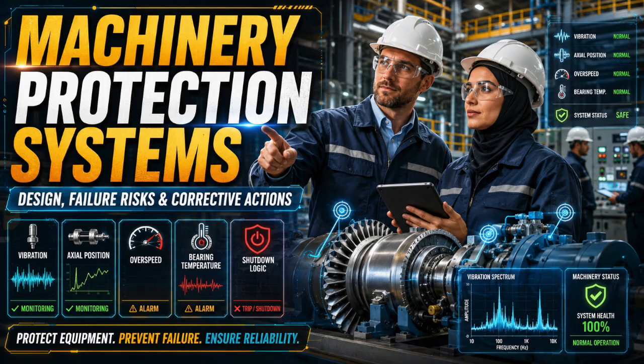Is overspeed segregated? Are speed sensors independent? Are power supplies redundant where required? Are hazardous area requirements addressed? Can the system be maintained safely? Are spares defined? Are calibration records available? Are field test records available? Are as-built drawings complete? If you cannot answer these questions, the system is not fully engineered. It may be purchased, it may be installed, it may even be running, but it is not yet fully defensible.